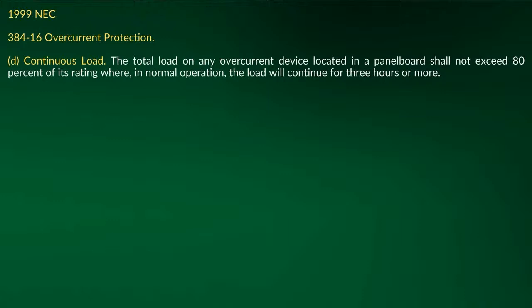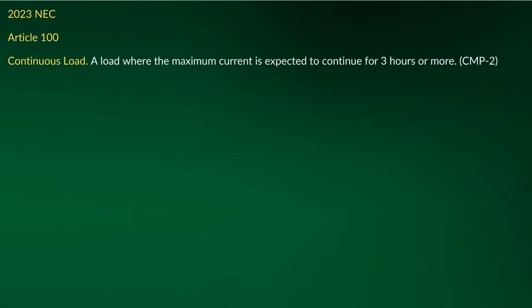And you'll remember we did a calculation before where I showed doing a continuous calculated load using method one. Then we did a method two, and I showed where you did an adjustment and correction factor at 100%. Yeah, and just before you were going to say that, I was wondering why they would take this out. But that makes a lot of sense, because there's no reason to derate things twice, just the same way there's no reason to GFCI protect things twice. That's right. And that's why all of this is being set up like this and why certain things were taken out. Now, when you go look at Article 100 just as it is now, it tells you a continuous load is anything that operates for what? 3 hours or more. Okay?